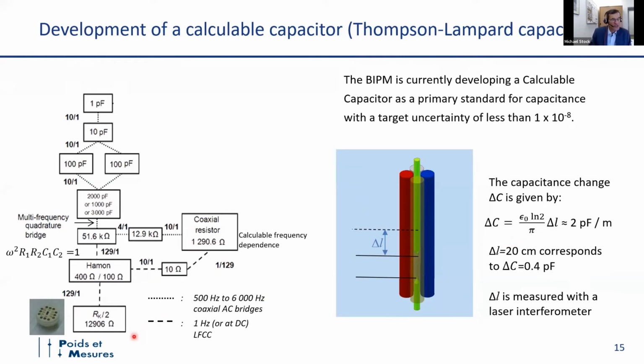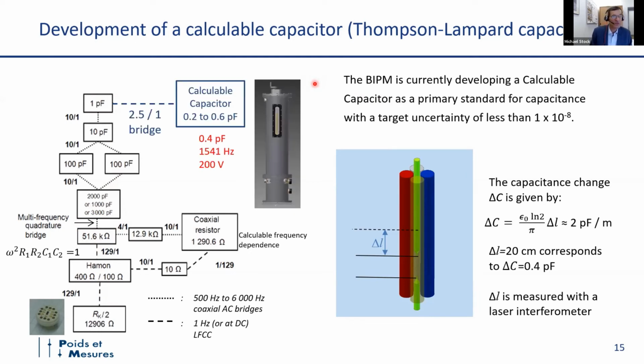You see here our traceability scheme from the Quantum Hall resistance, where we use the second quantized plateau, 12.9 kilohm. Then we go through a series of bridges operating at DC or very low frequency, around 1 Hertz. We have a multi-frequency quadrature bridge, which allows us to calibrate capacitors. And then we have a capacitance bridge, which brings us down by 10:1 ratios to 10 and 1 picofarad, which are the values which you use most. So you see the chain is very long, which builds up some uncertainty. The calculable capacitor is a primary impedance standard. So we would then get traceability directly at the level of 1 picofarad, which should allow us to obtain smaller uncertainties.